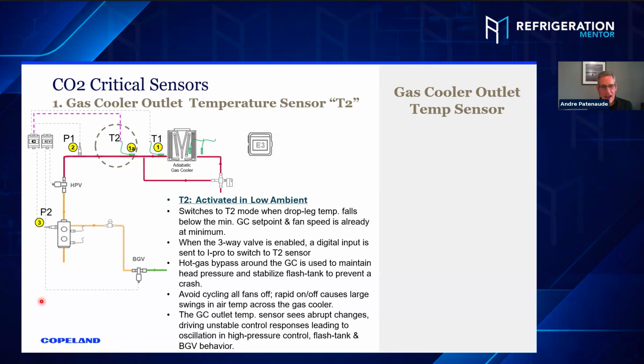Absolutely. So I've added this particular sensor, Trevor, since I did this presentation last. Of course, every time I look at a presentation, I change 4 or 5 things, right? So I shouldn't look at them. But anyway, this is a good thing. Someone asked me, "What about the T2 temperature sensor in low ambient?" And I said, yeah, you know what? I should add that. It might not be a critical sensor, but it's a sensor that's added, especially in Canada and the northern U.S., when you've got gas cooler bypass in the winter, when it gets so cold that even at minimum speed, you just cannot control your head pressures anymore.